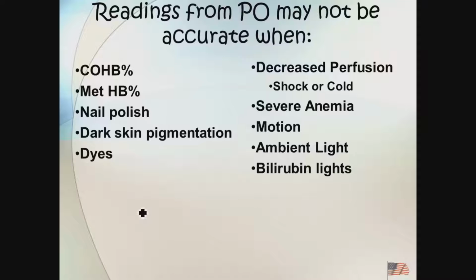There's also a lot of ambient light that is present there. They're also in a situation where they're perhaps cold. And as they get cold, their perfusion shuts down, so the accuracy of the pulse oximetry goes away. One other aspect of pulse oximetry, and we'll talk about this when we talk about the disease retinopathy of prematurity: if my saturation is 99 or 100%, what's my PO2? Something probably greater than 85 or 90. Could be 90, could be 300. I don't know. It's going to have the same saturation. Well, this becomes very, very problematic. So, good technology, but you've got to know what it's able to do.